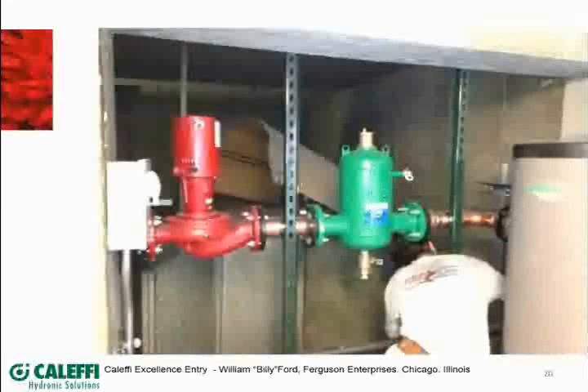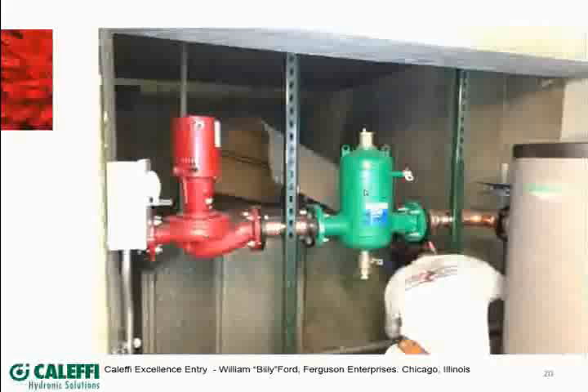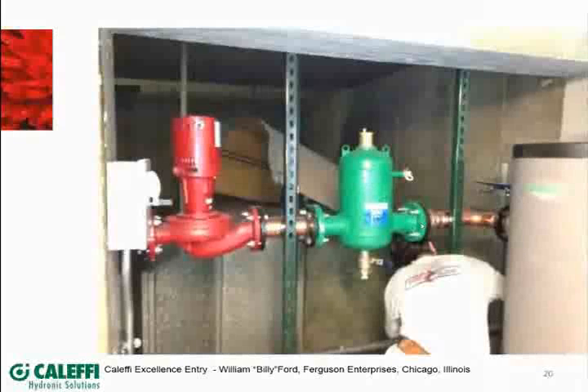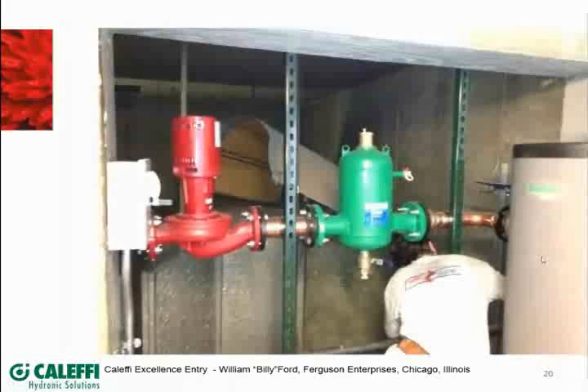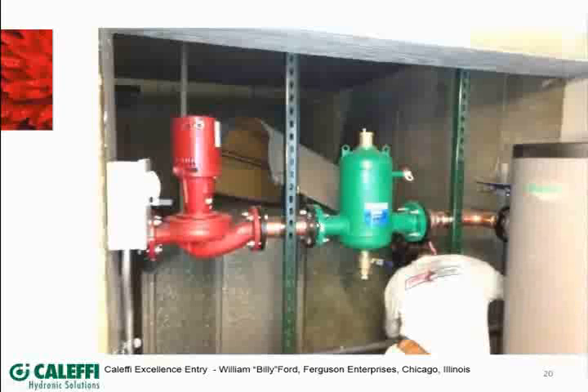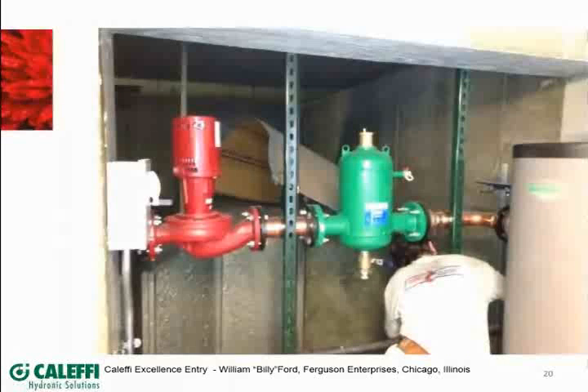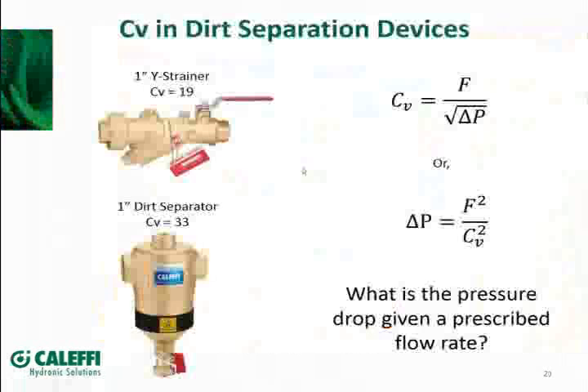Here's a picture from a job site that came in through a Caleffi Excellence entry. You can see a large pump pumping through a Discal air elimination device, with fairly close-coupled piping. Unlike a scoop-type air vent, this device does an excellent job even when closely coupled to both the pump and a buffer tank separator. This also shows that on site the test ports are not going to be at the same distance as the ISA-specified test bench dimensions, so the readings won't match exactly what we developed the CV number to.